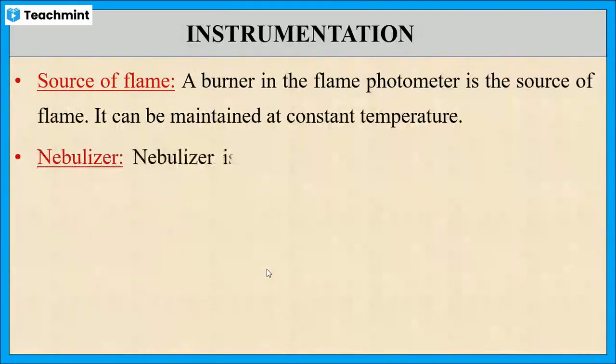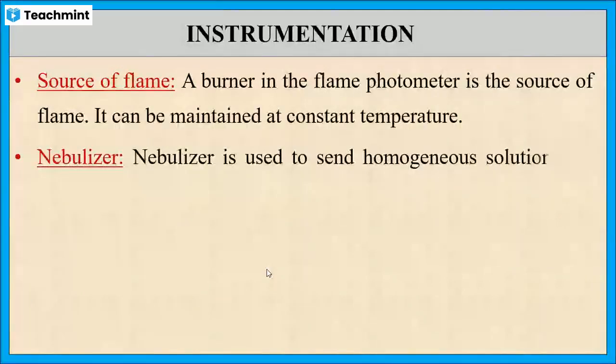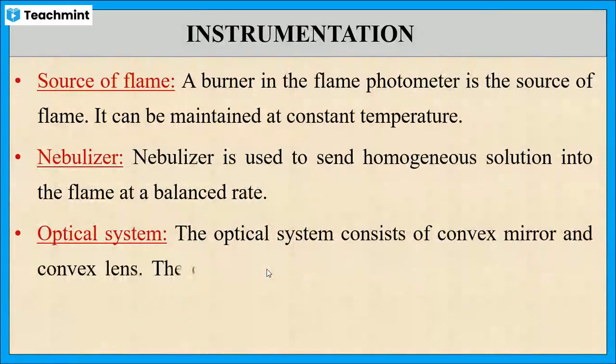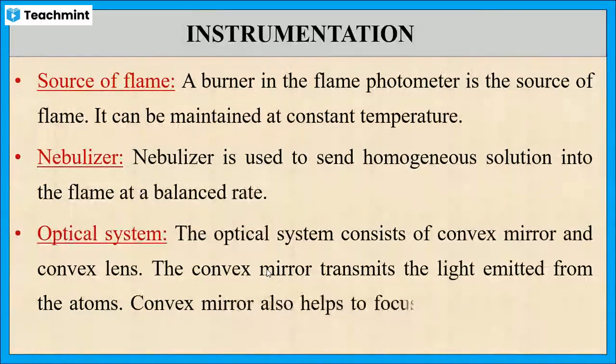Here the source of flame is the burner in the flame photometer. The role of nebulizer is to send homogeneous solution into the flame at a balanced rate. The optical system consists of convex mirror and convex lens which is helpful to focus the emitted light into slit of the filter.